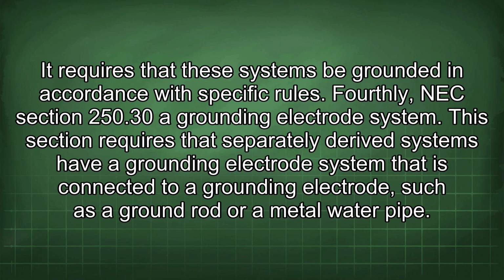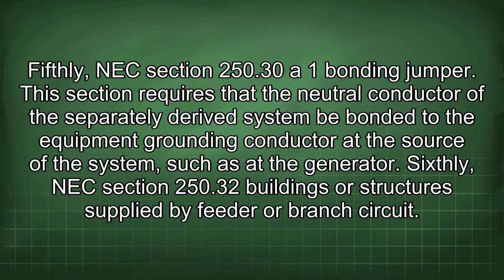Fourthly, NEC Section 250.30(A) Grounding Electrode System. This section requires that separately derived systems have a grounding electrode system that is connected to a grounding electrode, such as a ground rod or metal water pipe. Fifthly, NEC Section 250.30(A)(1) Bonding Jumper. This section requires that the neutral conductor of the separately derived system be bonded to the equipment grounding conductor at the source of the system, such as at the generator.